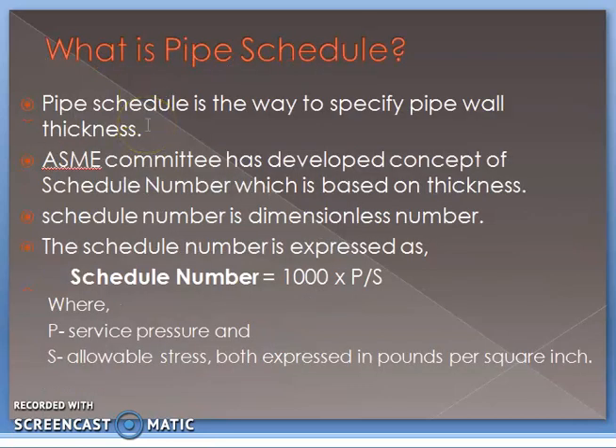Pipe schedule is another dimensionless number used to specify the pipe wall thickness. The American Society for Mechanical Engineers developed the concept of the schedule number, which is based on wall thickness. The schedule number is expressed as 1000 × (P / S), where P is the service pressure and S is the allowable stress. Both P and S are expressed in pounds per square inch (psi).